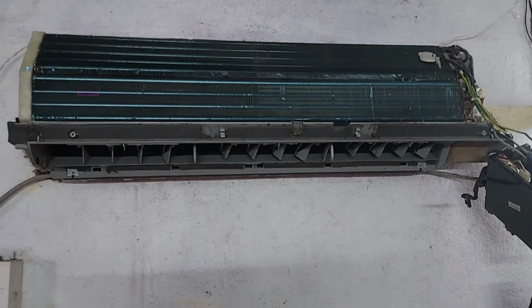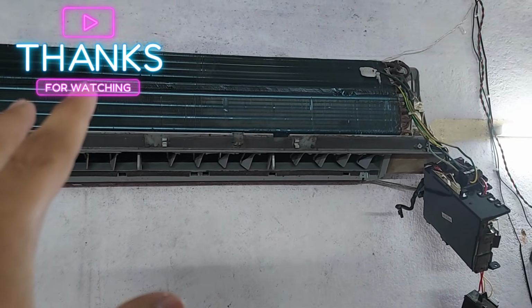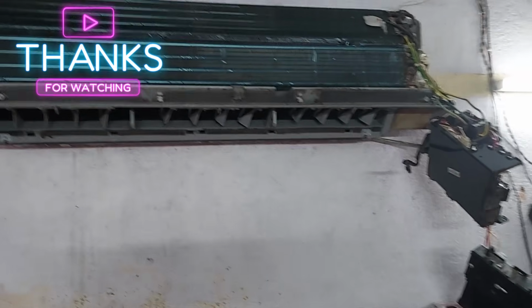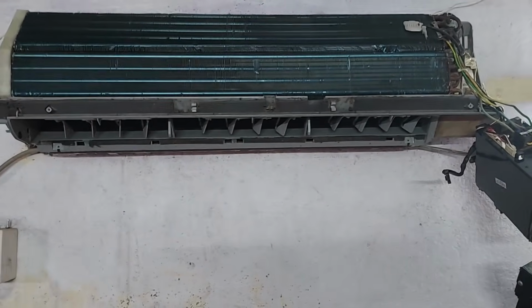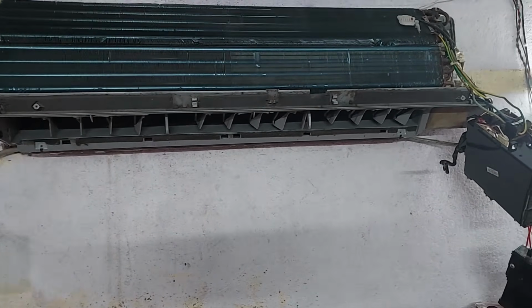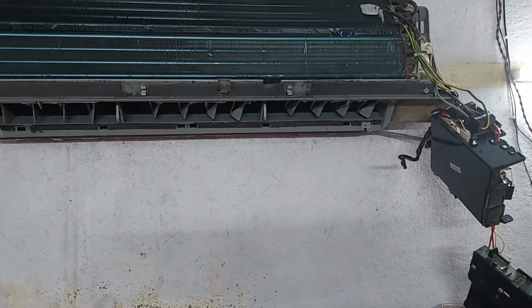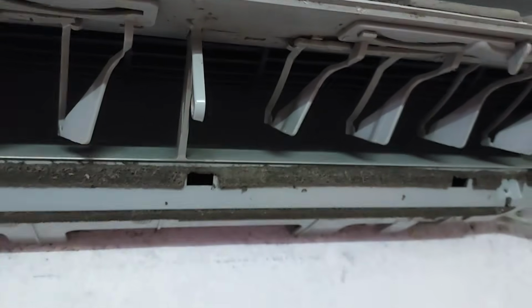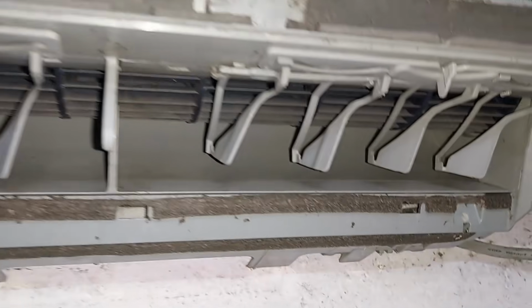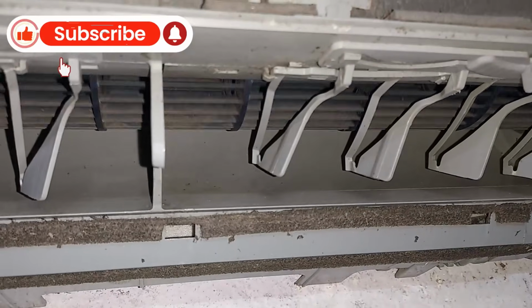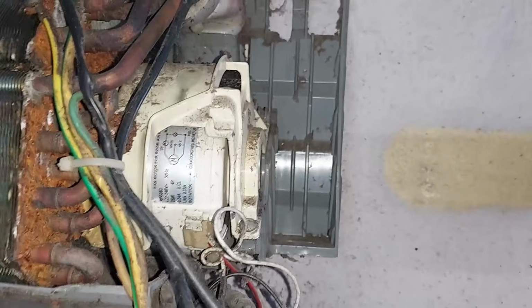It's your buddy Technoboy, and that's a 1.5 ton air conditioner. It's a non-inverter air conditioner. So this thing was having a problem with the E3 error, as E3 error is mainly caused by the indoor blower motor, which is right there. As you can see, that's the blower, and that's the motor of it.